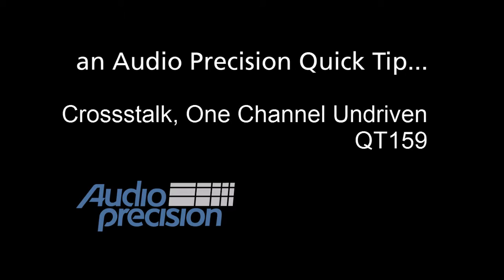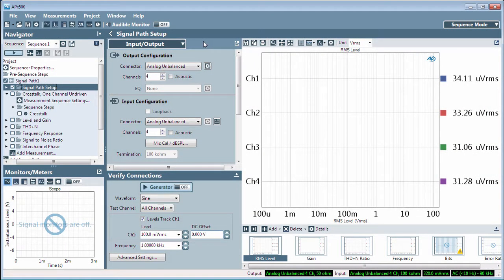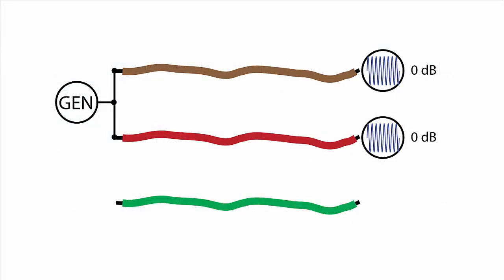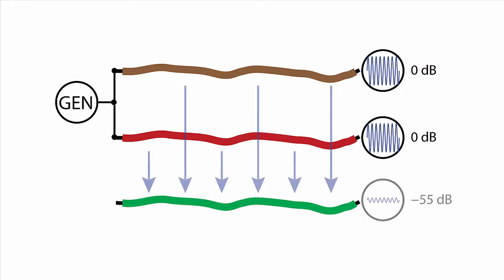In this quick tip, we're going to take a brief look at the Crosstalk one-channel UnDriven measurement in APX 500. Crosstalk is unwanted leakage or bleed of a signal from one or more channels into other channels within a device. Crosstalk one-channel UnDriven provides a measurement of the crosstalk into an unstimulated DUT channel when all other channels are stimulated.